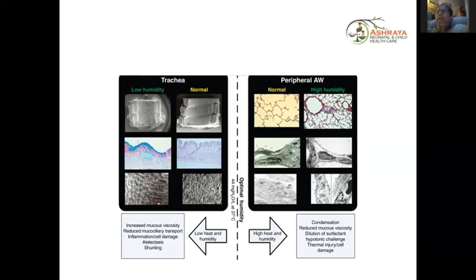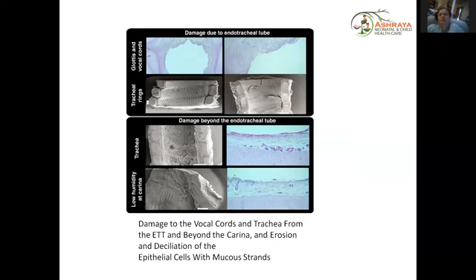So you can see the difference in the pictures, where there is damage to the vocal cords and the trachea from the ETT also, and beyond the carina, and there is erosion and deciliation of the epithelial cells with mucus strands. So clinical situations with suboptimum conditions we should also consider, like ambient air conditions. For example, if air outside is warmer, the humidifier produces less temperature to compensate. So then the humidification reduces, and hence it can lead to further issues.